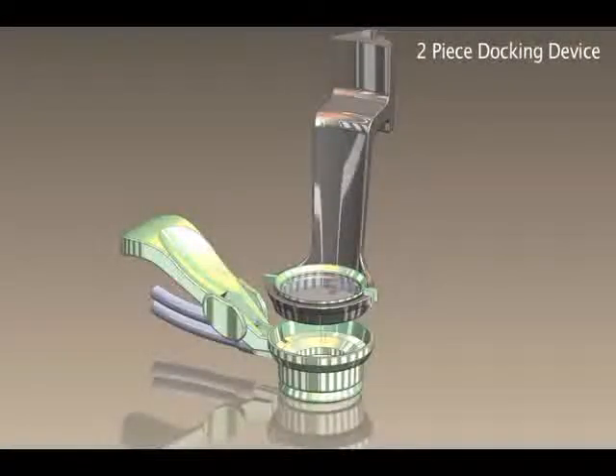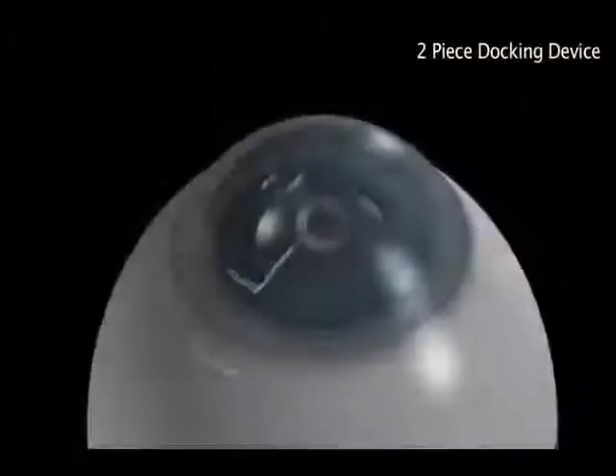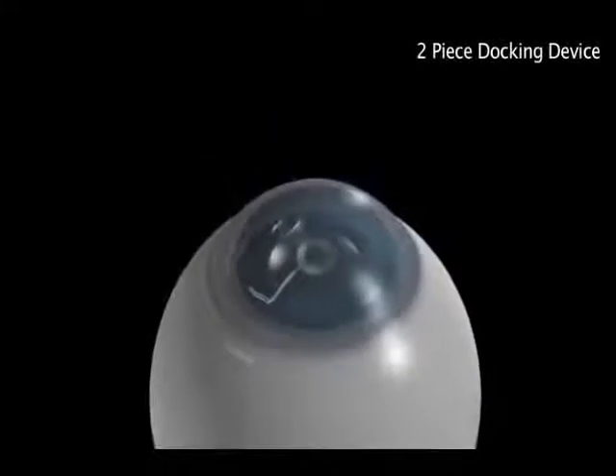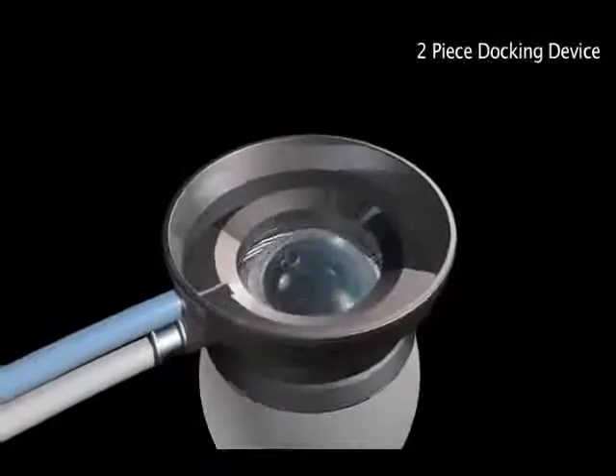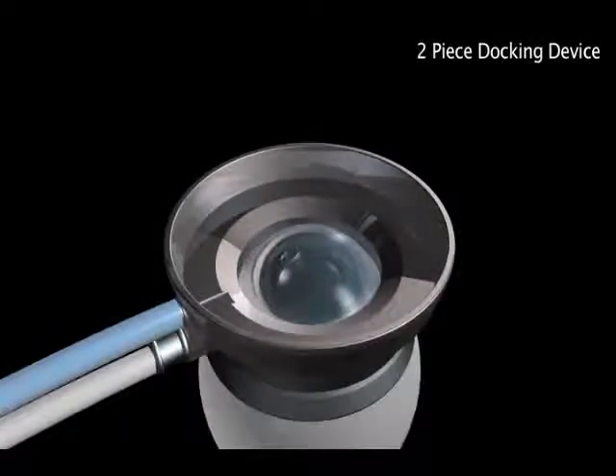Patient docking with the LENSAR laser system is achieved with a two-piece docking device that does not contact the cornea. Since there is no contact between the interface and the cornea, the cornea remains unstressed and does not show evidence of corneal folds that would otherwise reduce the quality of the subsequent imaging.